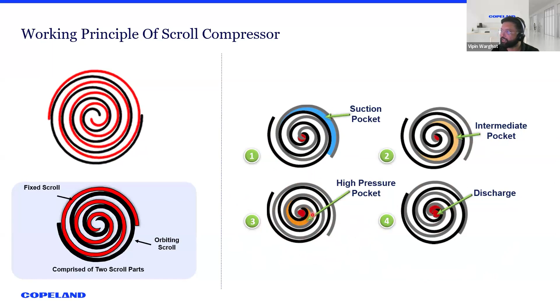As the orbiting scroll moves around the fixed scroll, it creates various pockets. The suction pocket is where low-pressure vapor refrigerant first enters the compressor. Then there's an intermediate pocket that starts the compression process, followed by a high-pressure pocket stage that further increases the pressure of the refrigerant. The fourth stage is discharge, after the high-pressure refrigerant is generated.